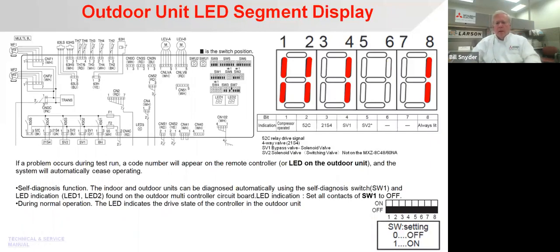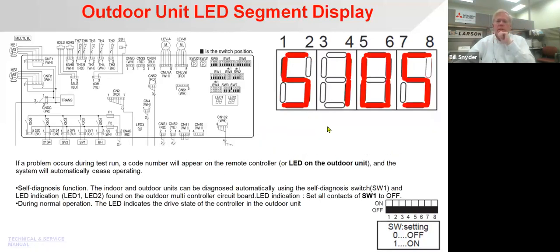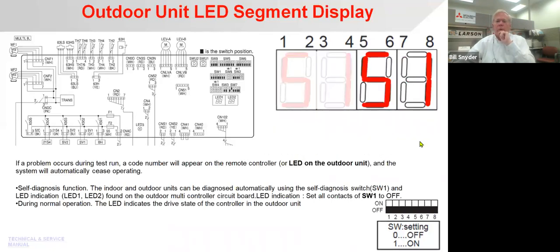However, if you take SW1 here, and I'll show you in a second how to change these switches, which are showing down here, 0 is off and 1 is on. If you turn these on and off different ways, we can make this display read other things. And if it goes into a failure mode and sends a signal, it could take up to 20 minutes for it to throw a signal. So a good idea, when you first get to one of these, is to open up the panel and look at this and see if there is some sort of a display that looks like this. This says 5105. It would be back and forth between 51, 5105, 51, 5105.